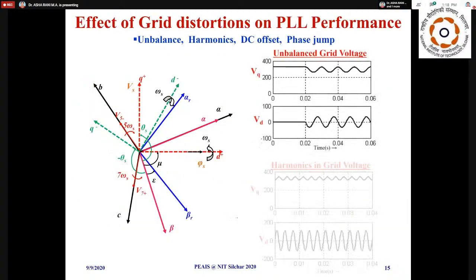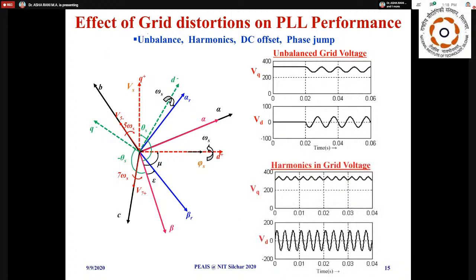I'll quickly tell you the effect of unbalance. During unbalance, you will have an additional component of 100 Hertz signal. If unbalance is present in the grid, you can see some 100 Hertz oscillations coming. Basically, inside the machine, as we studied for induction motor operation, the flux rotates in the clockwise direction. During unbalance, an additional flux starts revolving opposite to that, and these two interact with each other.